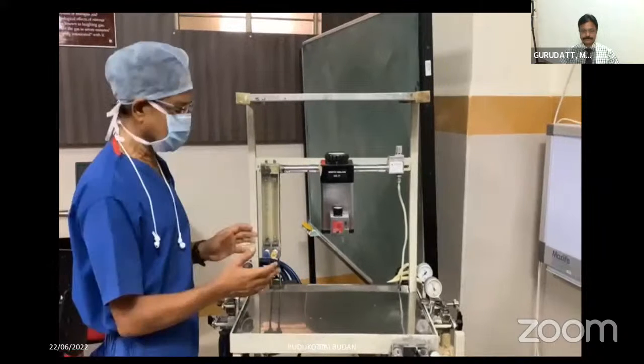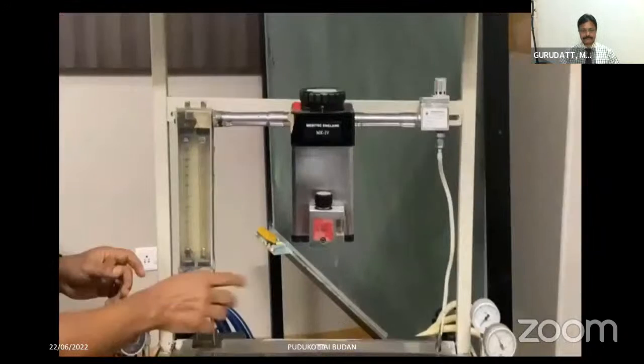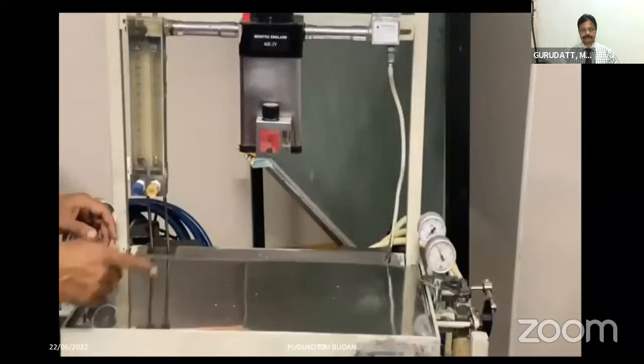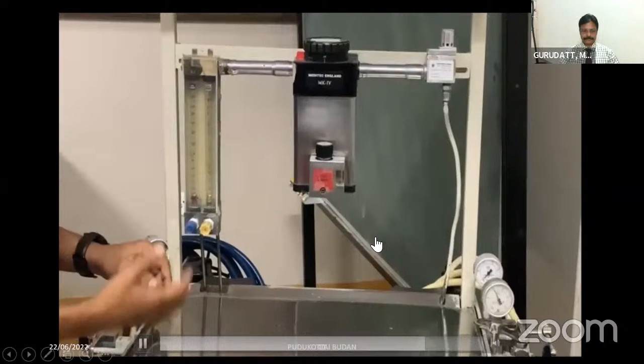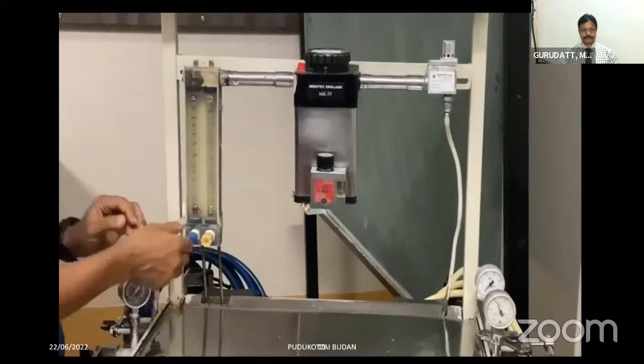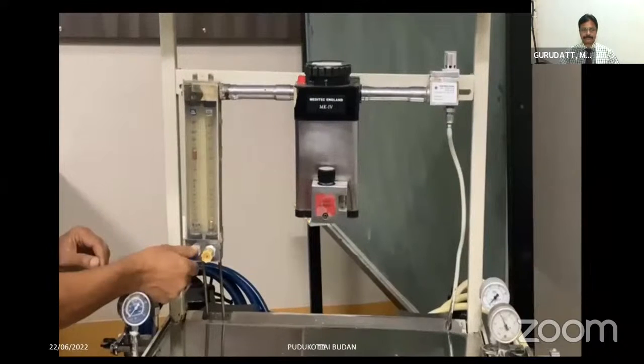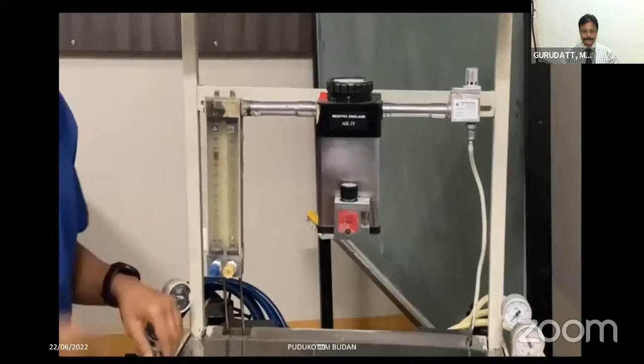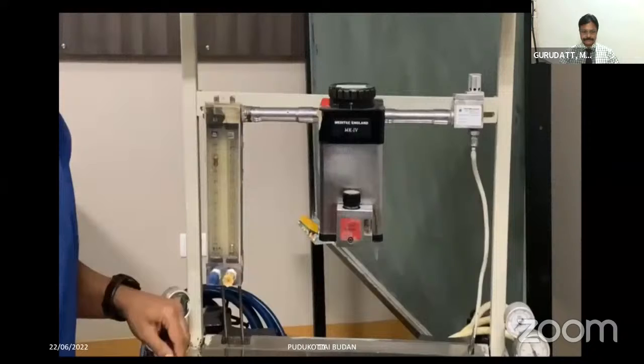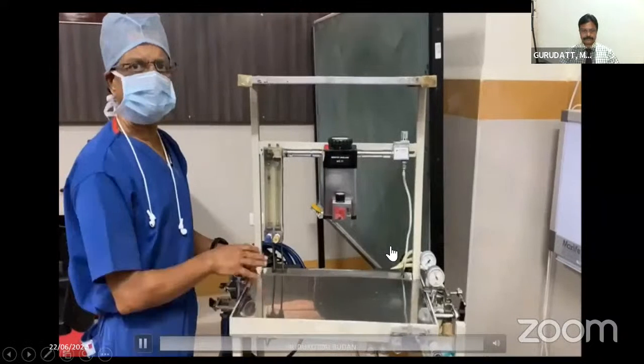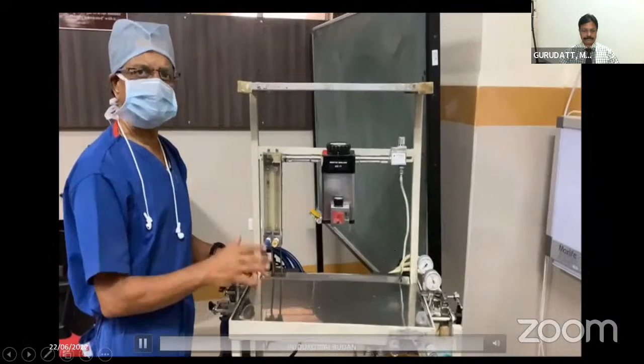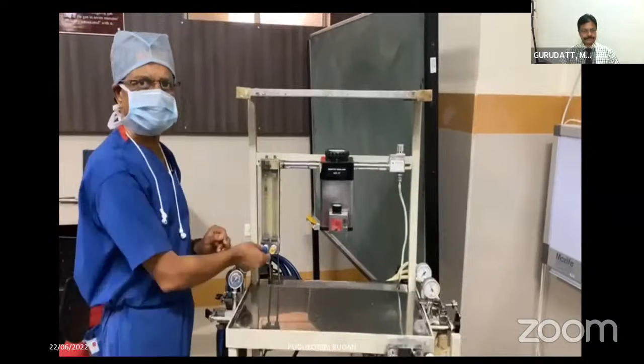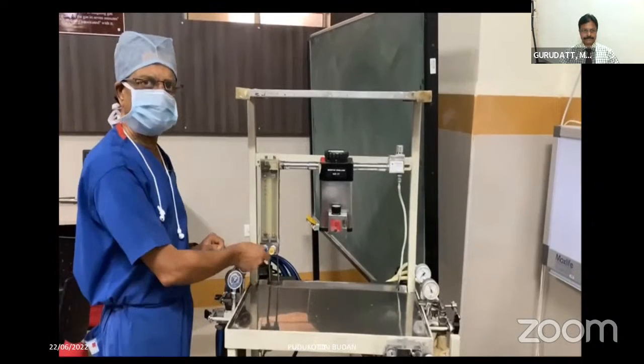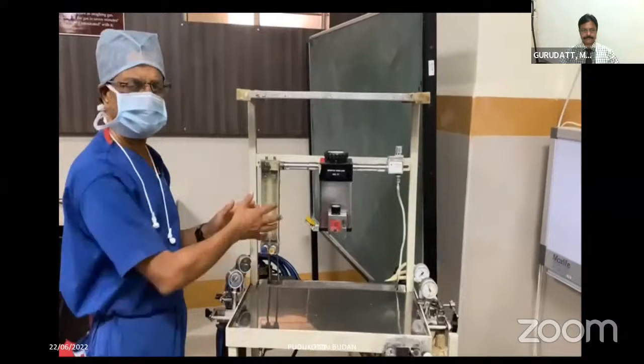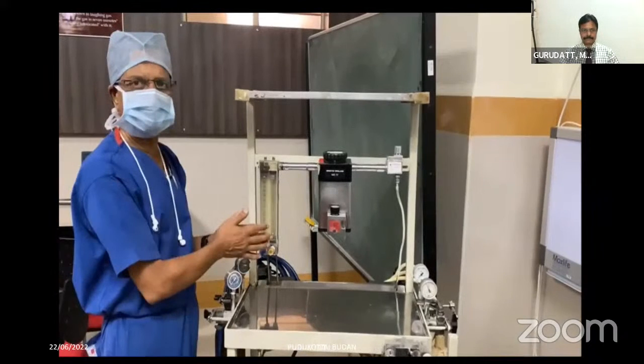I'll just demonstrate with this. So now I've opened the oxygen cylinder. Now oxygen pressure is there, which is passing through the nitrous oxide regulator, and it has opened the nitrous oxide pressure regulator. With this, I can still give only nitrous oxide. See, now I have opened up only nitrous oxide. I can still give the patient only nitrous oxide without oxygen, and definitely that is going to produce quite a bit of hypoxia. So in order to prevent that, we have the proportioning devices at the flow meter level, which I am going to discuss later.